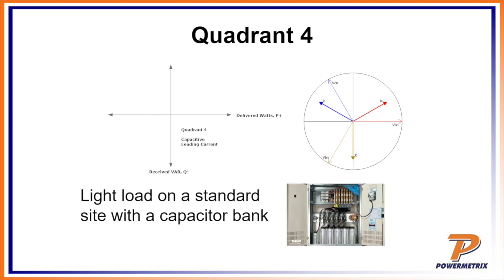Lastly, quadrant four, this could be a solar site, but probably not. This is more likely a standard commercial site with a leading power factor. Most of the time we see this in quadrant four when you have either a substation or a customer down the line with an idling capacitor bank. That's right, and that causes that leading power factor.